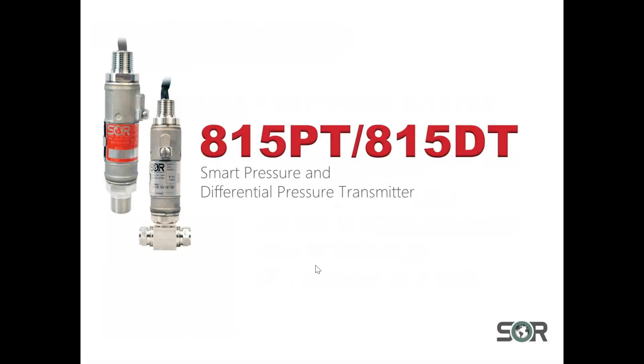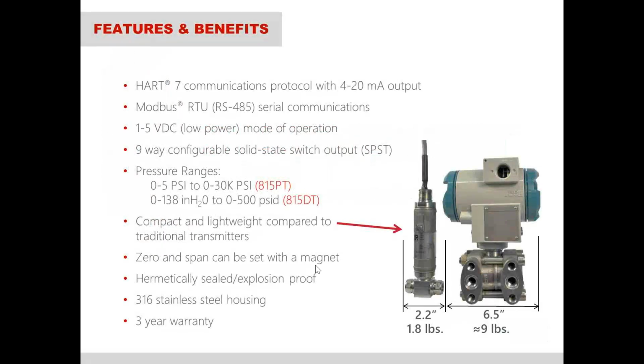Moving on to the 815 PT and 815 DT. The 815 PT and DT offer a lot more different options and features, all in the same package, whether you ask for it or not.